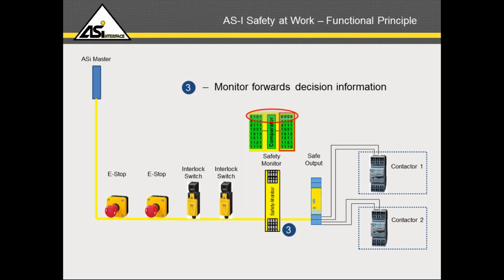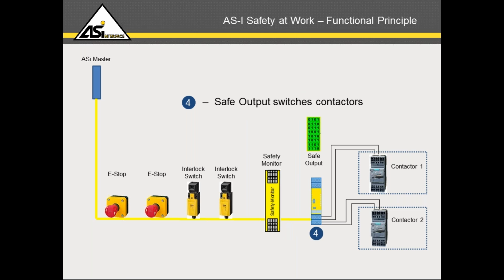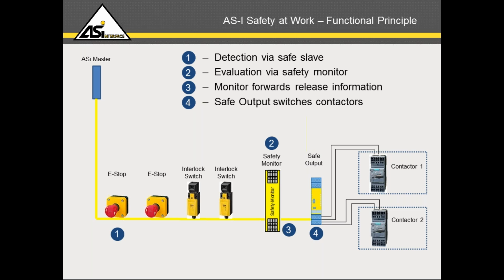In this case, the top 4-bit sequence in the received code table is different from what was expected. So the safety monitor is going to tell the safe output device to shut down the contactors, because that's how we parameterized it. The safe output device, having received the command to shut down its outputs, again, because it's a unique 32-bit code sequence, we know that it's that output device that's going to react. It switches the contactors off and effects a safe shutdown of the machine.